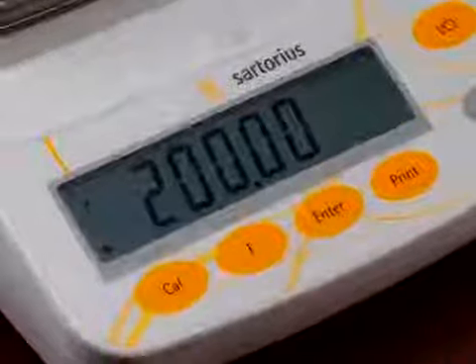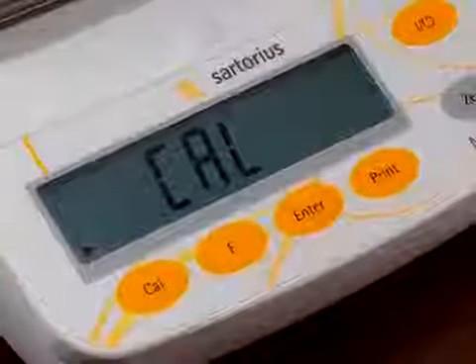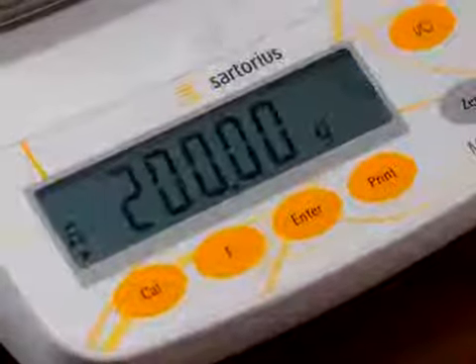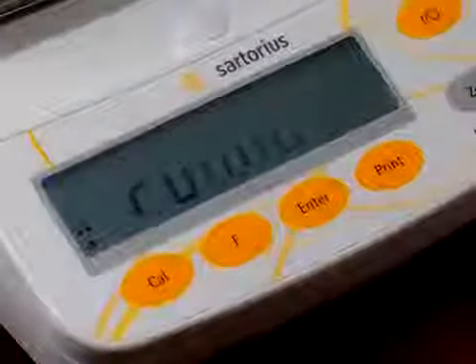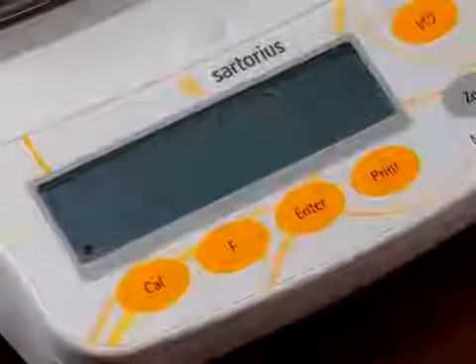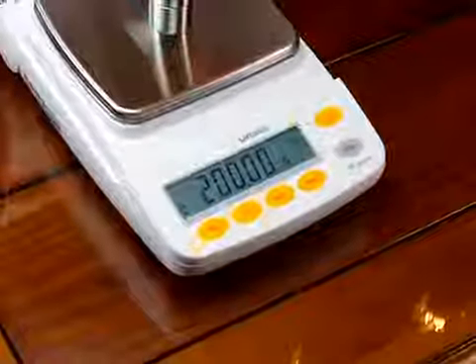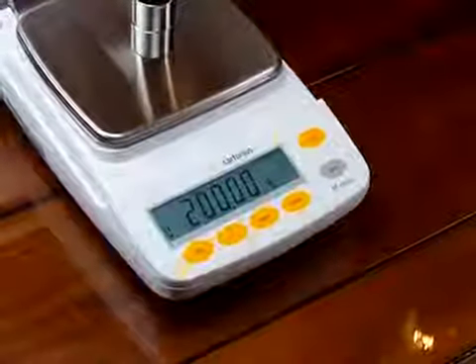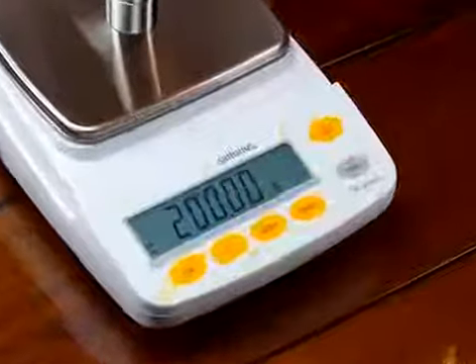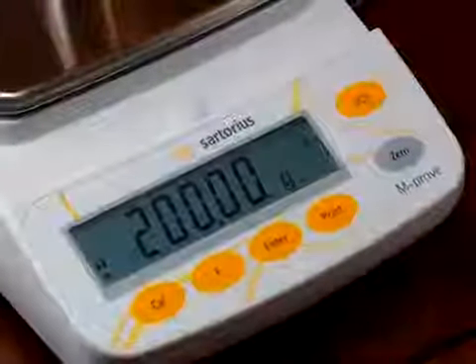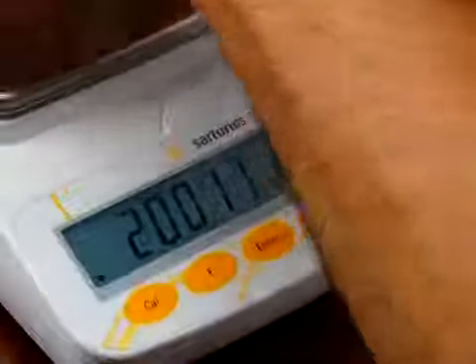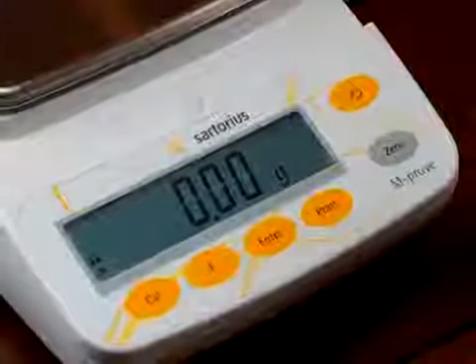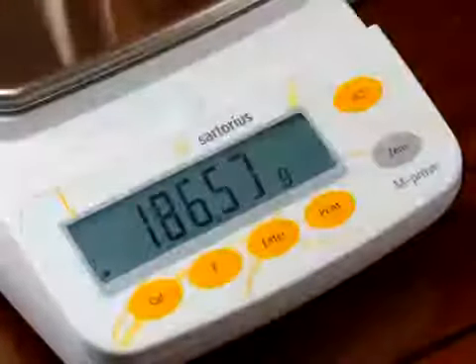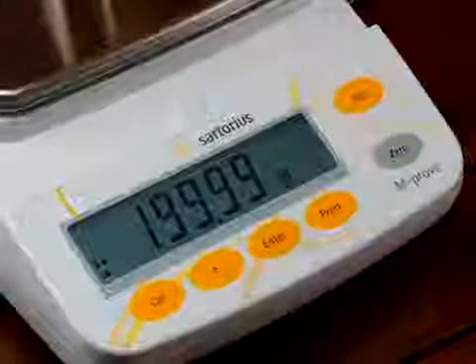And now you want to hit the Enter key. The balance says cal, and it starts to flash 200. We want to put our 200-gram weight right in the center of the balance. You'll notice the balance flashing, and all of a sudden it reads 200, and it's steady. So the balance has now been calibrated, and if we remove the weights, you'll see the balance goes back to 0, and the balance is now calibrated. There it is, 200. It's going back and forth.